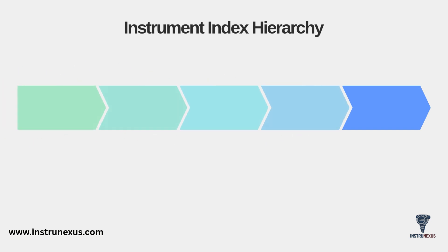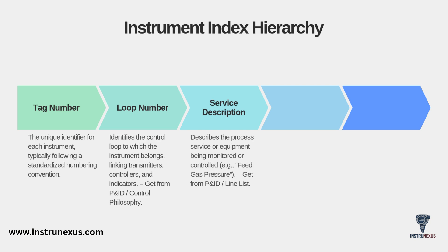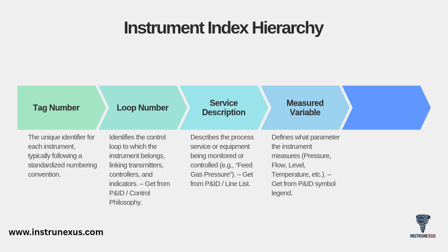Now let's talk about the data itself — the Instrument Index Hierarchy. These are the columns in your database. First, the tag number: the unique identifier for each instrument, following a standard numbering convention. Next, the loop number, which identifies the control loop the instrument belongs to, linking transmitters, controllers, and indicators — obtained from the P&ID or control philosophy. Then the service description, describing what it's monitoring, like feed gas pressure. You'll also list the measured variable, like pressure, flow, or level, and the instrument type, such as transmitter, indicator, or control valve — both taken directly from the P&ID.